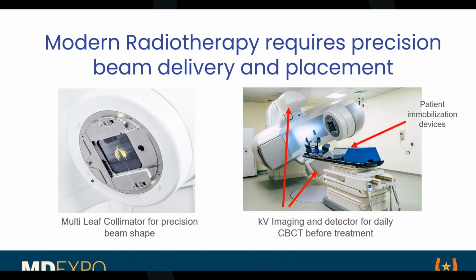And then on top of all this, we also have imaging devices. We have a kV imaging device on the linear accelerator to do a cone beam CT. So before we treat the patient, we can do a cone beam CT and compare that to the CT that we did at the planning, and say, okay, the patient's here, here's where we want them to be, and then we can automatically move and position the patient correctly. And so then we know that the patient's in the right place.